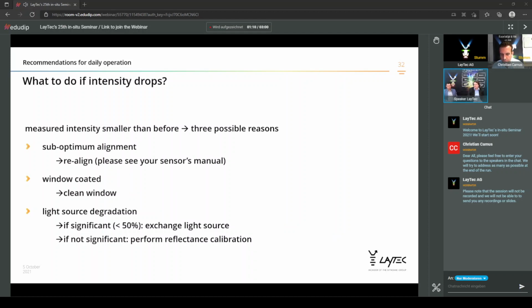It depends on the amount of coating. Sometimes even cleaning it with a Q-tip with IPA might be sufficient. Depends. And as mentioned, if the light source degradation is really significant, that means, and this is also mentioned in your calibration protocol, less than 50% of the initial intensity, we strongly recommend to start to exchange the light source, contact LayTec or contact Aixtron. If you are still able to work, this is the right time to start to get the replacement part.